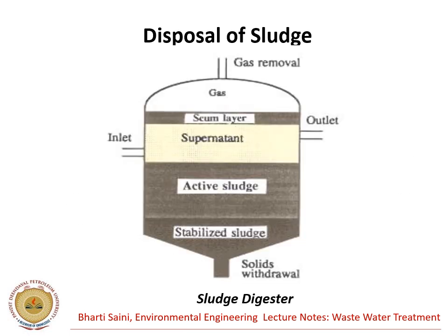This is the typical layout of the sludge digester. You can see the circular tank, which has a hopper shaped bottom and is equipped with a roof. It may be fixed or floating in nature. When the tank is put into operation the first time, it is required to be seeded with digested sludge from another tank. Also, the raw sludge is first pumped into the tank.